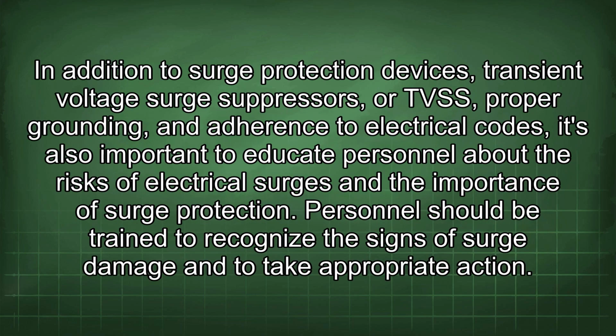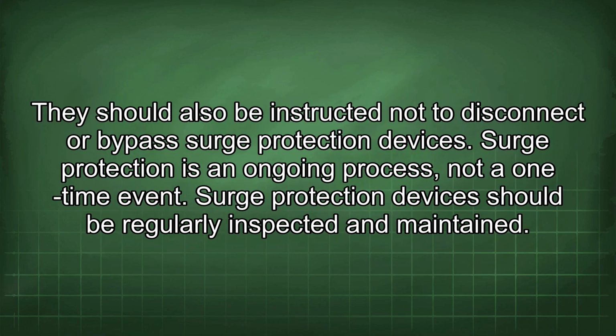In addition to surge protection devices, transient voltage surge suppressors, or TVSS, proper grounding, and adherence to electrical codes, it's also important to educate personnel about the risks of electrical surges and the importance of surge protection. Personnel should be trained to recognize the signs of surge damage and to take appropriate action. They should also be instructed not to disconnect or bypass surge protection devices.